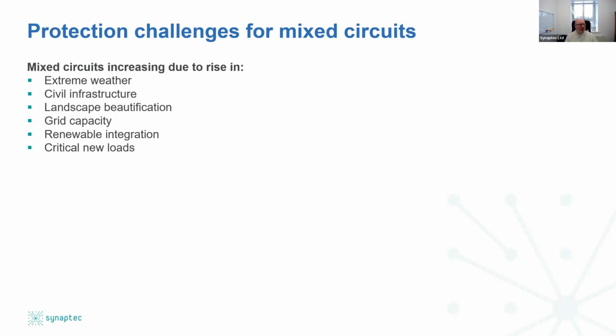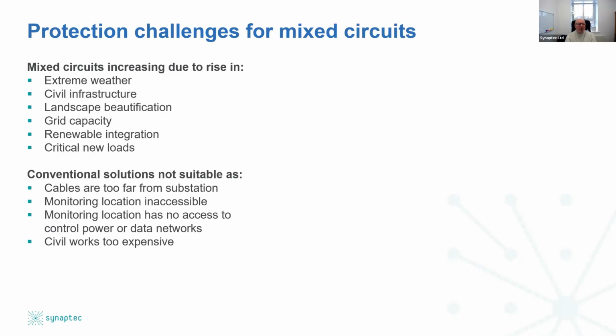Sometimes it's about congestion capacity, or indeed integrating renewables and critical loads. Whatever the reason is, I think everyone knows there's an amazing amount of cable production and installation work going on around the world. And from a protection perspective in the grid, cable sections within a circuit present a unique challenge, because sometimes these cable sections could be quite far away from the substation, and that monitoring location could be very remote or inaccessible. And maybe there's no substation there, maybe there's no access to telecoms, maybe there's difficulties obtaining power supplies. So it's very difficult to reach very far out of the substation.